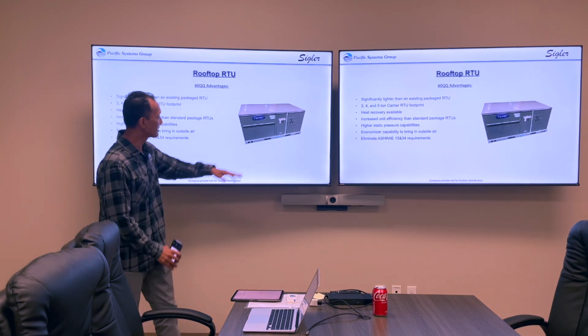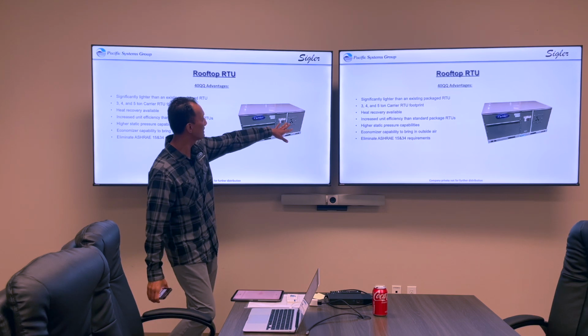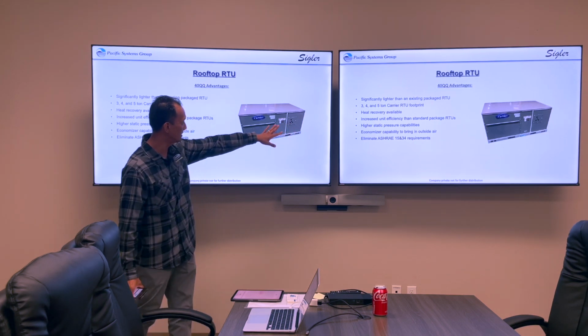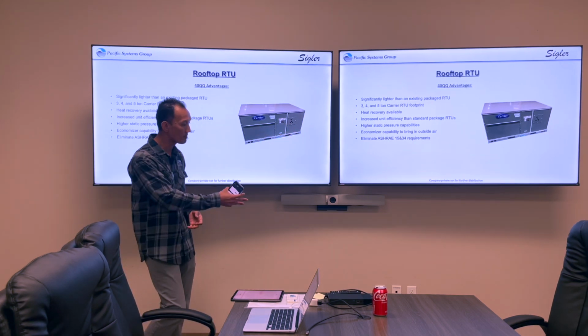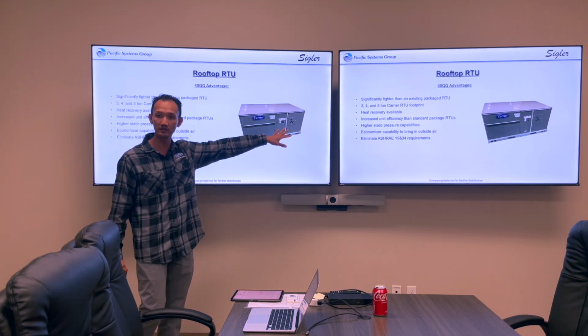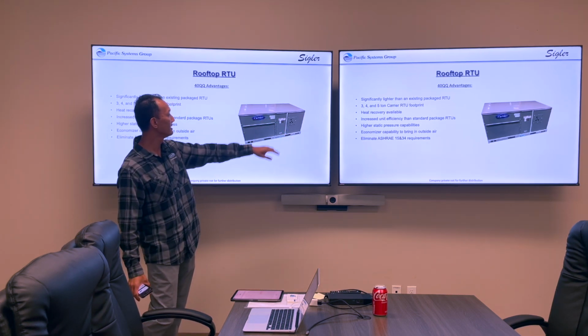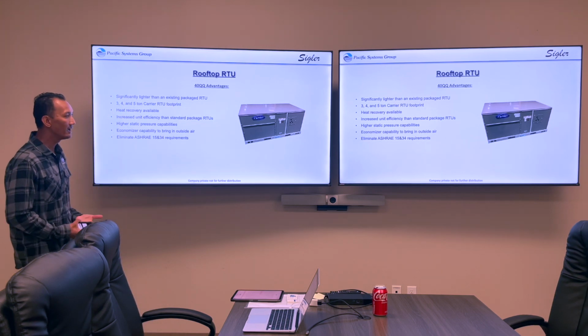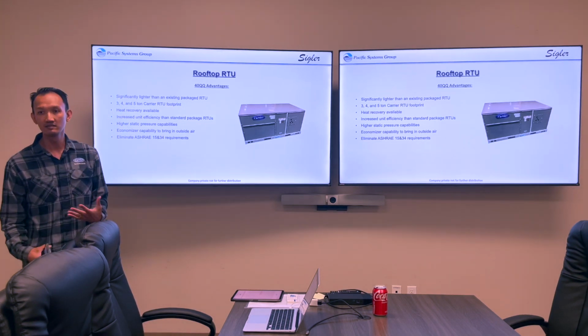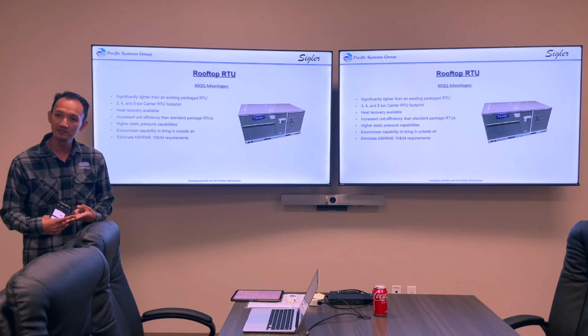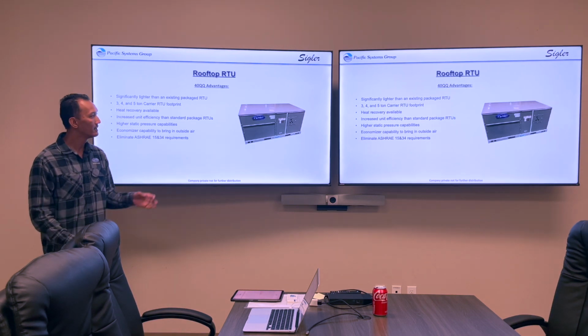You can use these for heat recovery. You can see there's the 3 holes there on the side of the panel, on the side of the unit. So just 3 pipes into there. You can install the flow selector box, like a single port box, inside one of those things. And now the building owner has an updated system, has a more efficient system since it's using VRF.